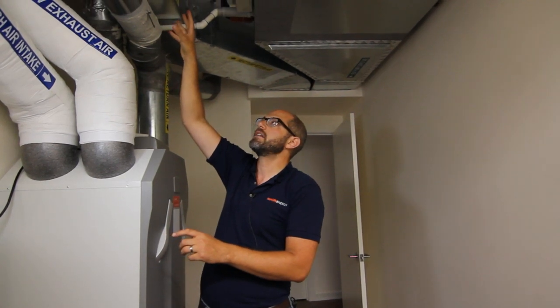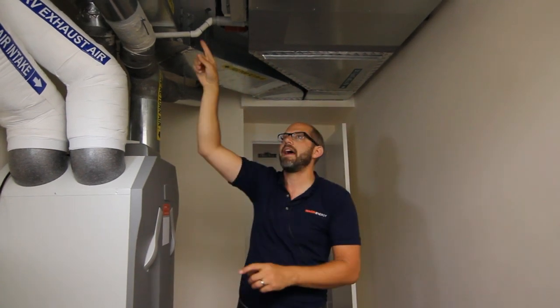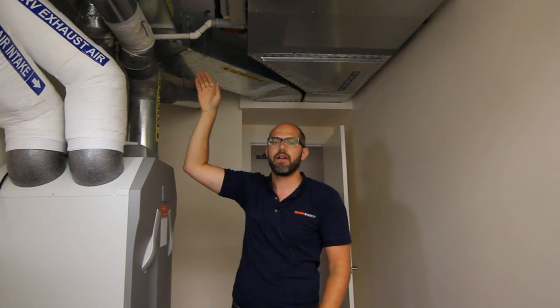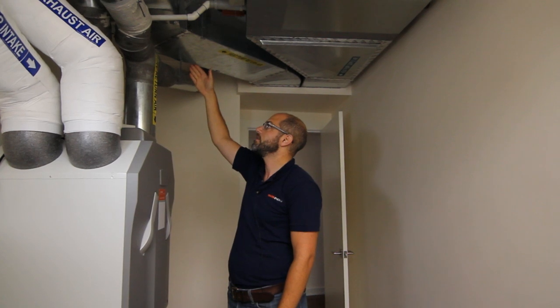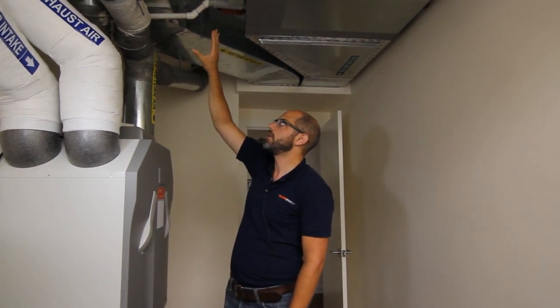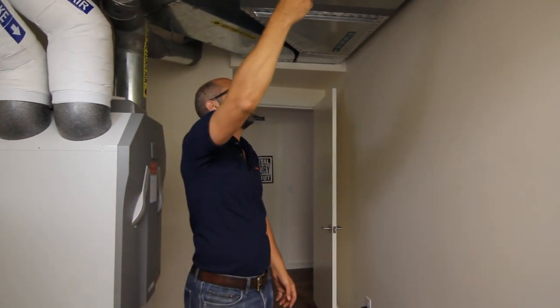The ventilation air comes in here. If we let it just come into that duct, it could go both that way, back out to the return, and that way to the supply. But we want it all going out the supplies and not out to the return. So we put in a little damper here that's actuated on pressure, and it will keep itself closed, pushing all of the fresh ventilation air out through the duct system and out to all of the rooms.